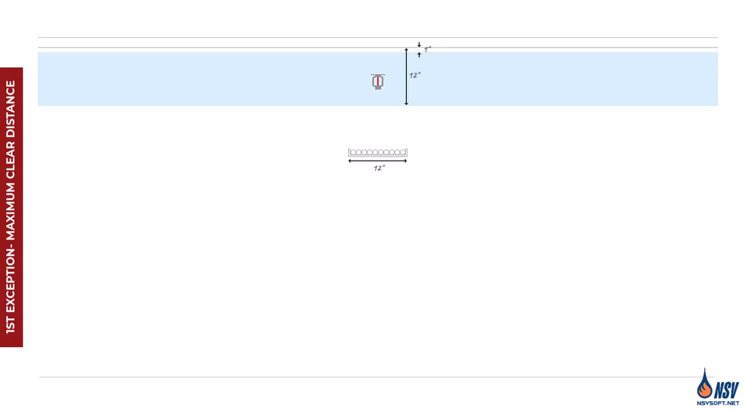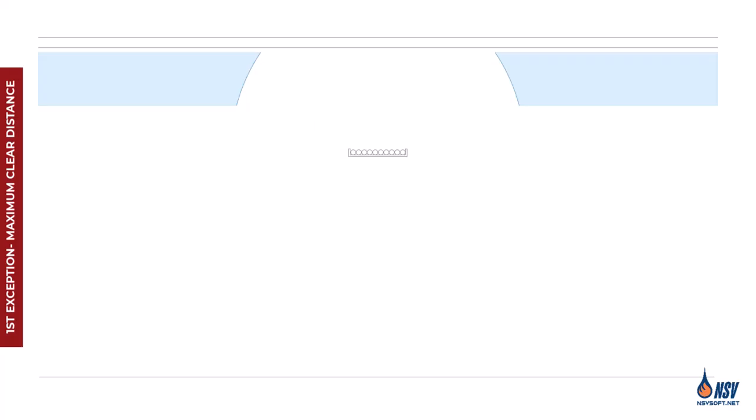Now imagine a cable tray installed 21 inches below the ceiling. Using the maximum clear distance rule, 24 inches, the allowable area for sprinkler placement becomes more limited. You might wonder, is the blue area the only acceptable zone for placing the sprinkler? The answer is no.